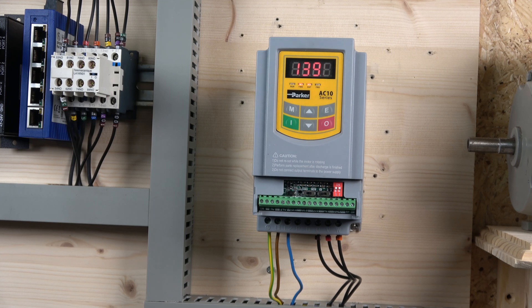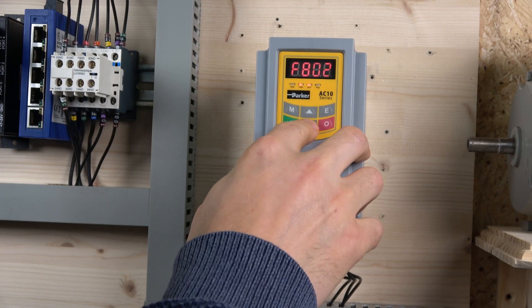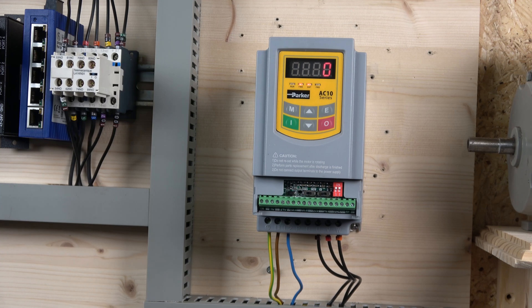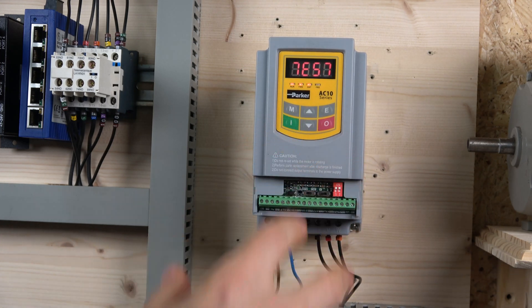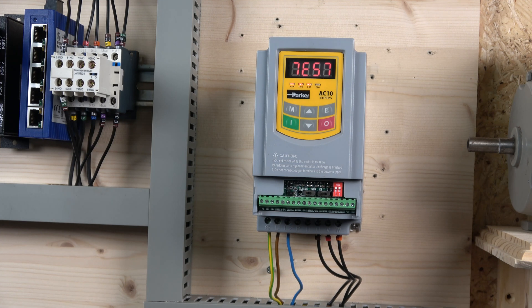Once motor parameters are entered, the only thing left is to do the auto-tune. Go back to parameter 802 to initiate it. There are two options: 1 is rotating tuning and 2 is stationary tuning. For rotating tuning you must disconnect the motor from the load — Parker is clear that the motor must be unloaded. Press enter and then press start, and the drive will begin auto-tuning, measuring resistances and motor characteristics. It completed quickly — the drive is now fully tuned and ready to go.